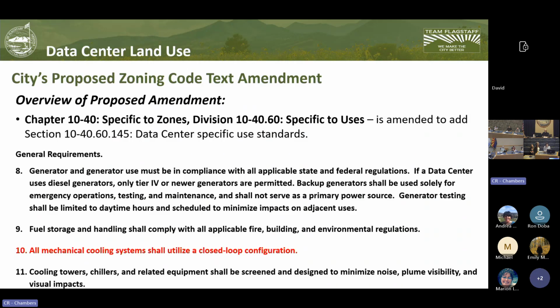She said that typically even a closed loop system has to be associated with a heat rejection mechanism, and that mechanism is usually water-based, most commonly a cooling tower. While the chilled water side of the system may be closed loop, the heat rejection side is typically open loop and will consume significant amounts of water through evaporation and blowdown, as well as additional losses from mechanical and operational issues.